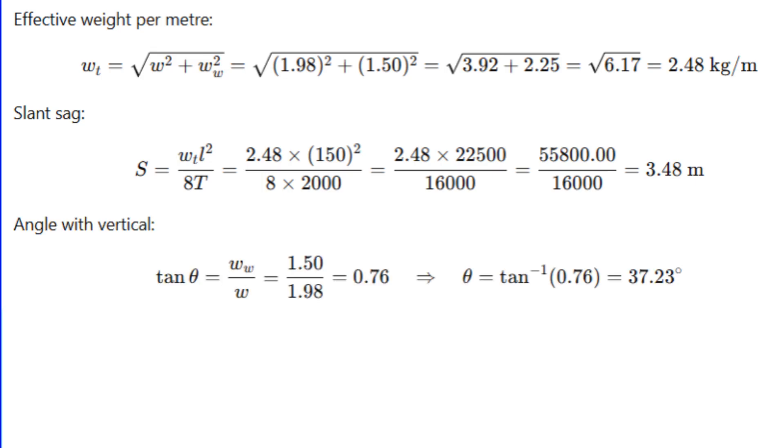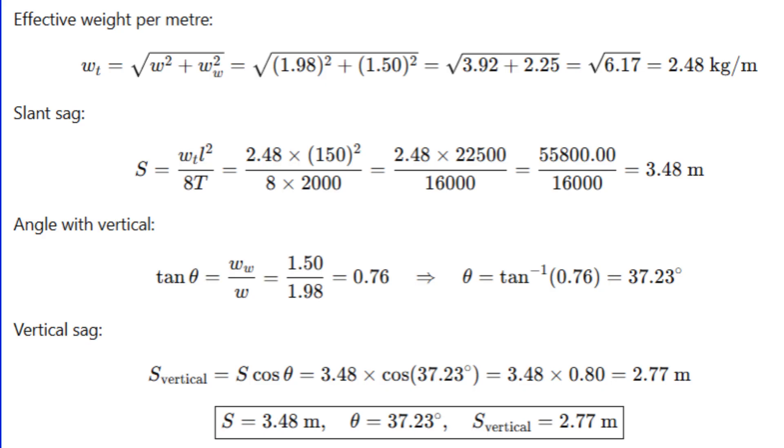Now calculate vertical sag: tan θ = ww/w = 1.5/1.98 = 0.76. θ = tan⁻¹(0.76) = 37.23°. Vertical sag = 3.48 × cos(37.23°) = 2.77 meters. So the vertical sag is about 2.77 meters. Pretty amazing, right?